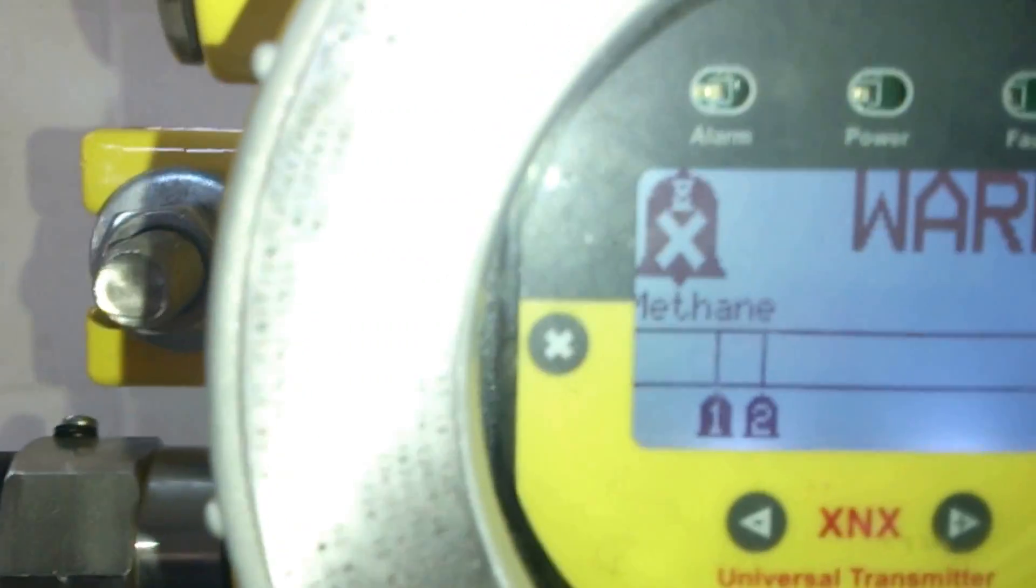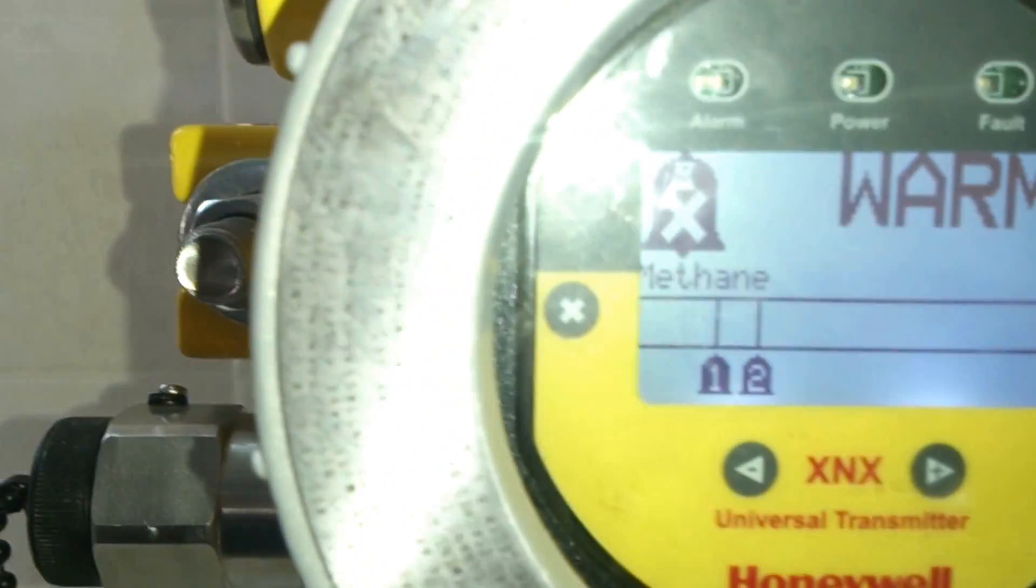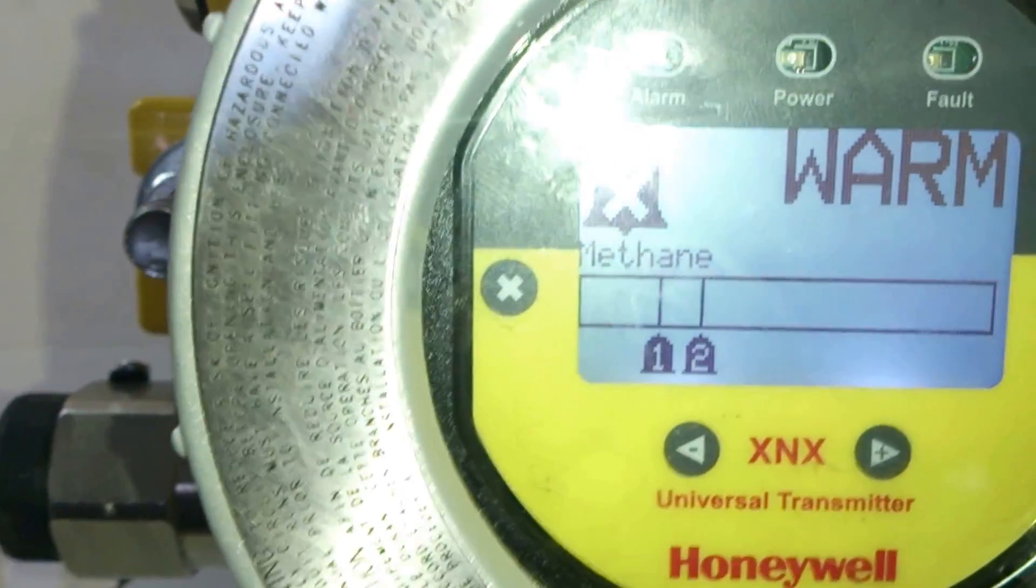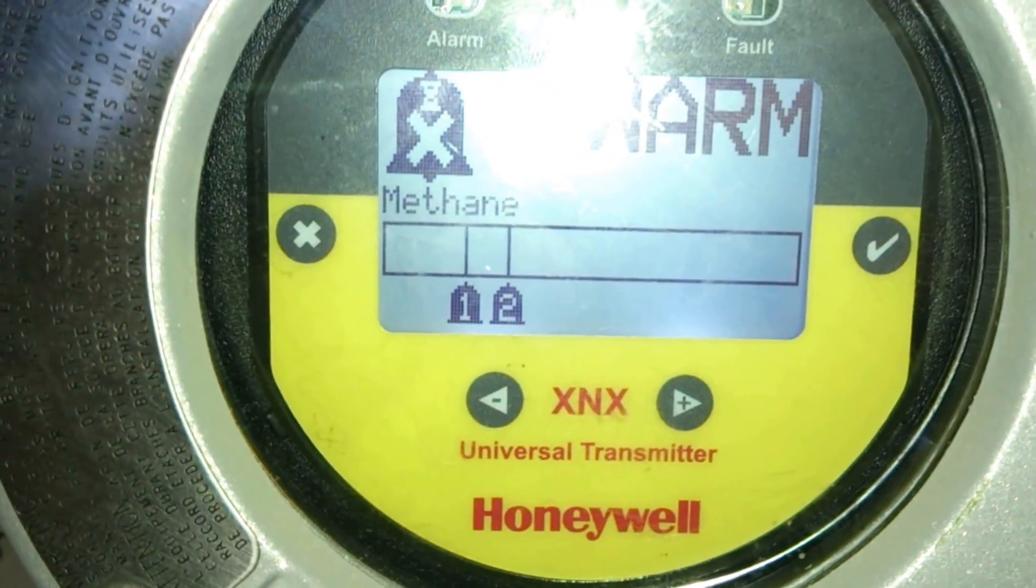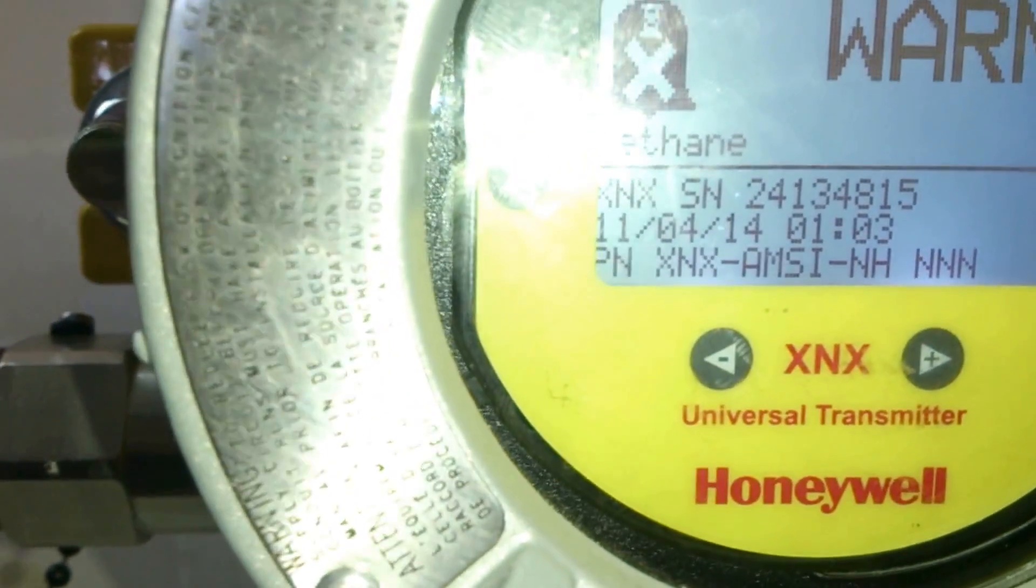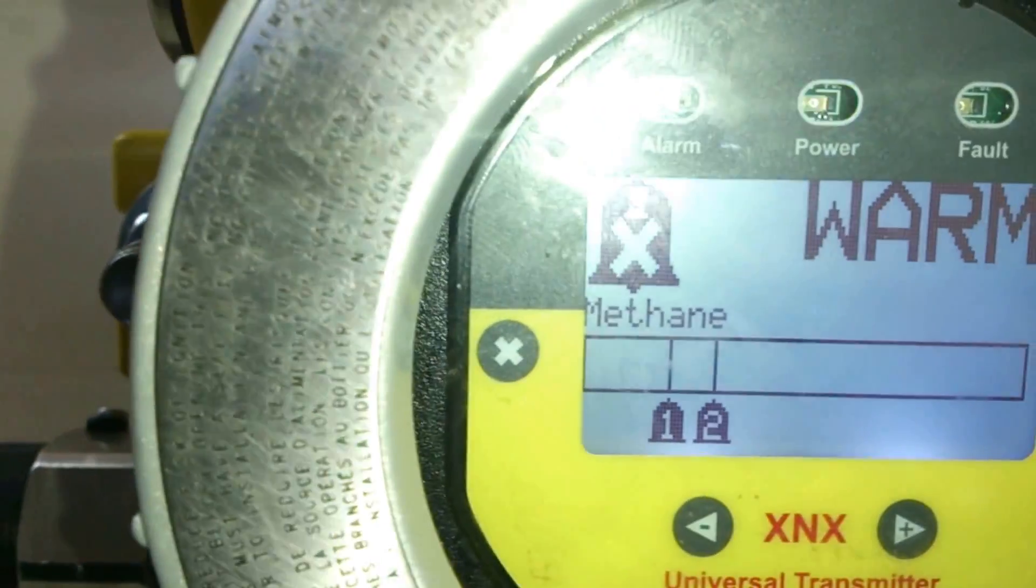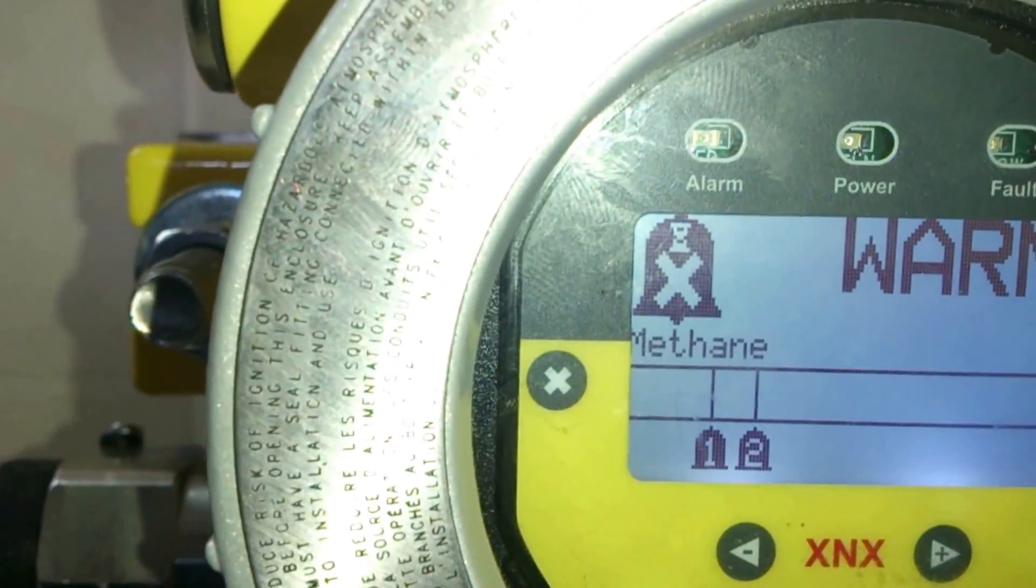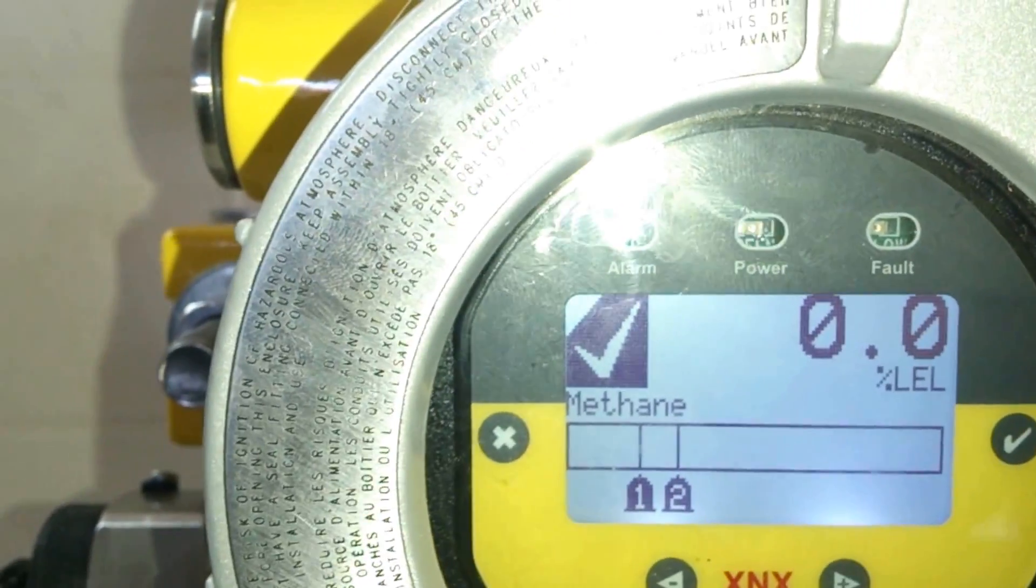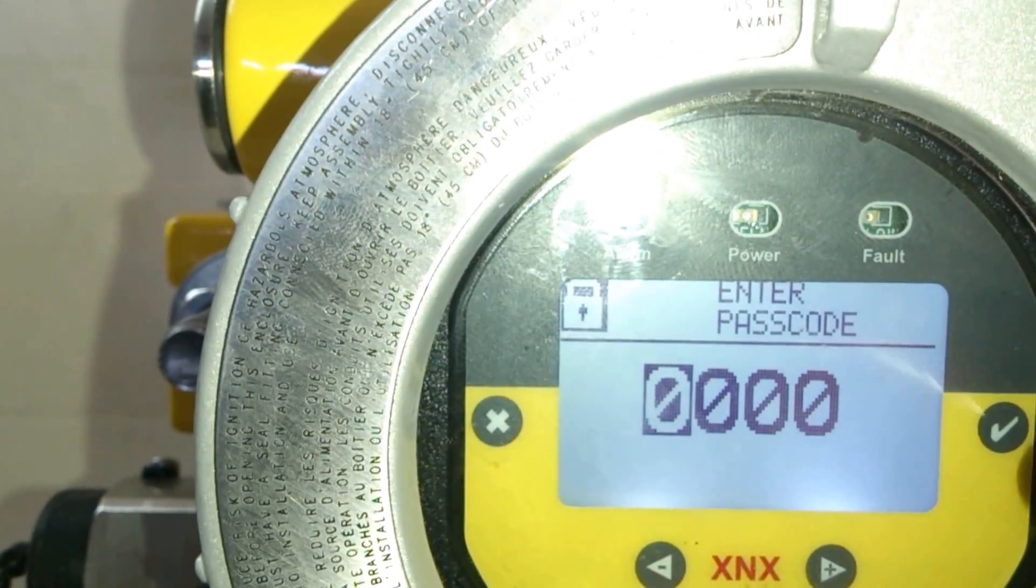The front panel of the XNX transmitter has an alarm indicator, a power indicator and a fault indicator. On the left it has an X mark to go back to the previous menu or cancel, and on the right we have a tick mark to select options. At the bottom we have minus and plus toggle keys which are used to increase or decrease values or to toggle between options. Once the warm up procedure is done we enter into the menu by selecting the tick mark. We enter the passcode that is 0000.